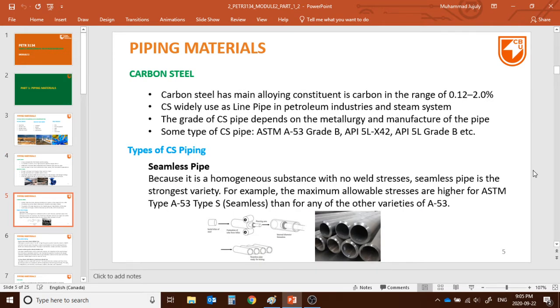Carbon steel is the most widely used material in pipelines, namely for oil and gas and chemicals — it's very versatile. Carbon steel's main alloying constituent is carbon, ranging from 0.1 to 2 percent, sometimes even 4 percent. Carbon steel is widely used as a line pipe. Always remember: line pipe means the main pipeline for oil and gas. It is used as a line pipe in petroleum industries and also as a steam system.